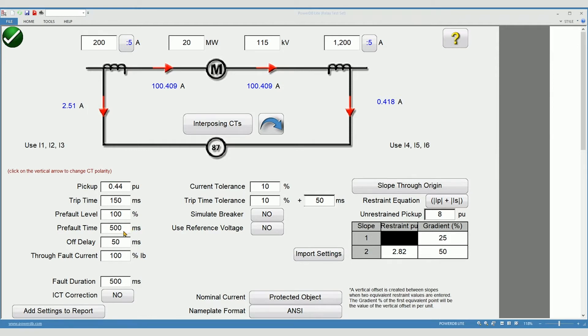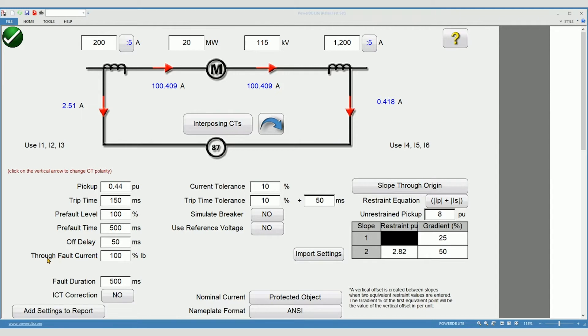The pre fault time, how long will this pre fault value be applied. The off delay is used in between fault pulses as the relay is tested. Through fault current determines how much current is applied to the relay during the stability test. Simulate breaker causes the test plan to keep current on after a trip is received long enough to simulate the opening time of a breaker.